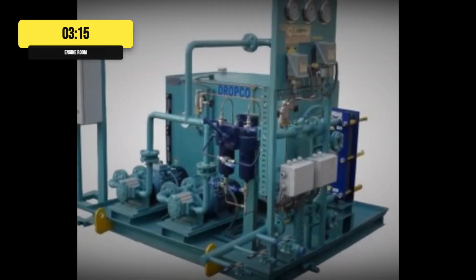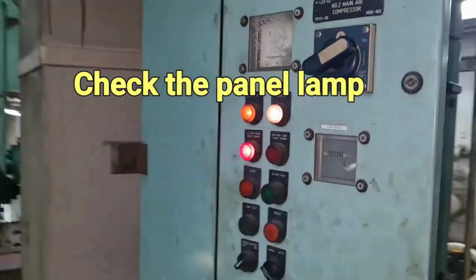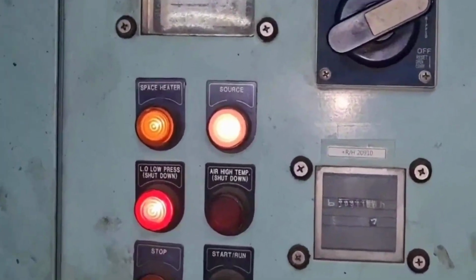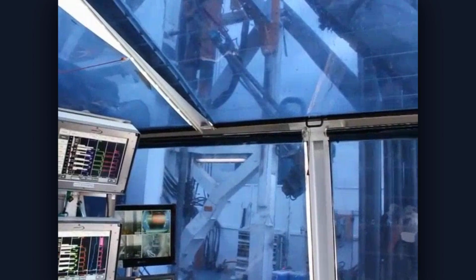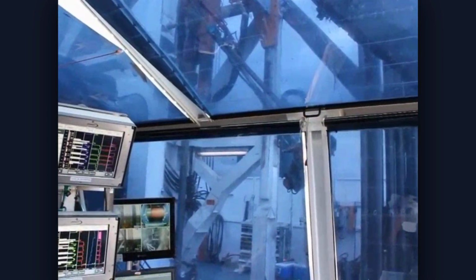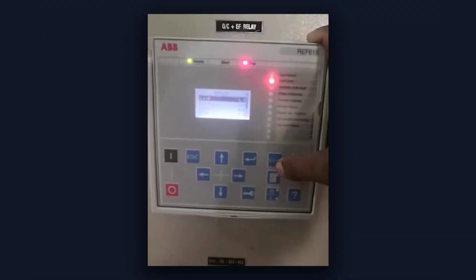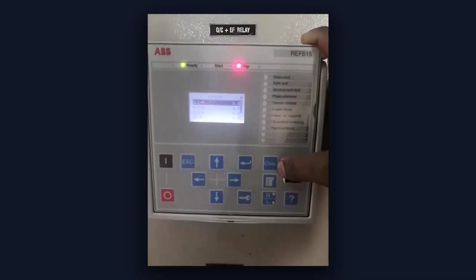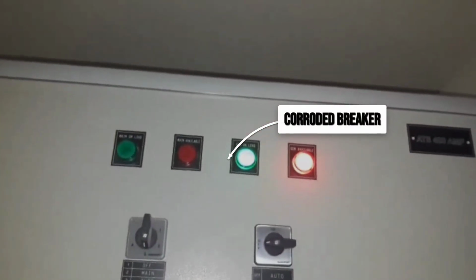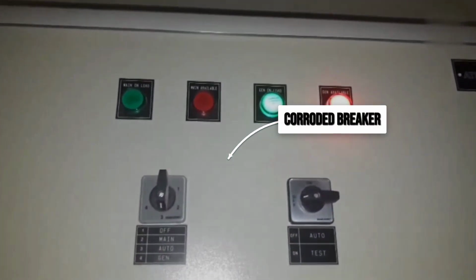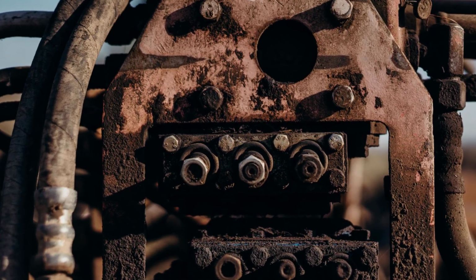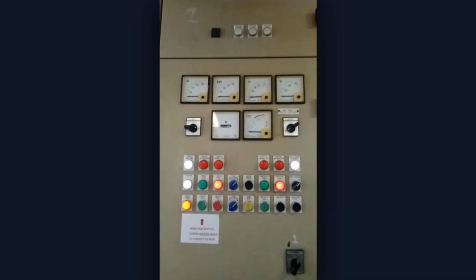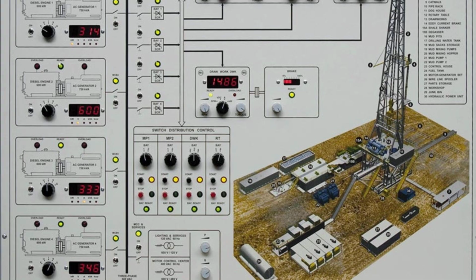At 3 minutes 15 seconds, a fault in the auxiliary lube oil pump forced a compressor shutdown. The main generator, already near its upper load limit, tried to absorb the sudden shift. Within seconds, protective relays tripped, dropping the platform onto emergency power. The automatic transfer sequence was supposed to bring a second generator online, but a corroded breaker on the hot standby unit blocked the transfer. Only the emergency generator remained, forced to shed all non-essential loads.